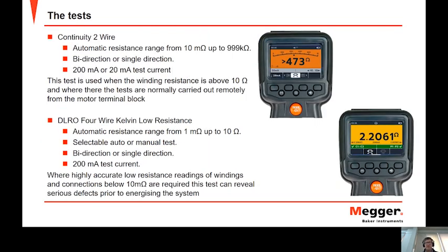We have a 2-wire continuity test that has a range from 10 milliohms up to 999 kiloohms and can be set to bidirectional or single direction. And we have 20 or 200 milliamp test current. We also have the 4-wire Kelvin resistance test, or the DLRO test, and that has an automatic resistance range from 1 milliohm up to 10 ohms with a resolution of 0.01 milliohms. And we have 200 milliamp test current for this test.